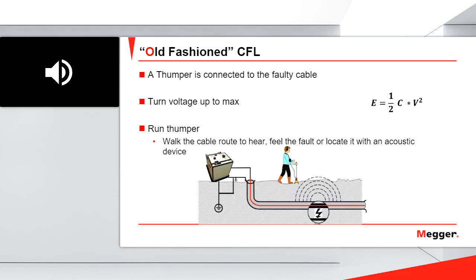Okay, talking of the old-fashioned cable fault location method, what was it and what did it consist of? Well, first we connected a thumper, a cable fault location equipment, to a faulty cable, and we turned the voltage up to the maximum, and then we started to send high voltage pulses through the faulty cable.